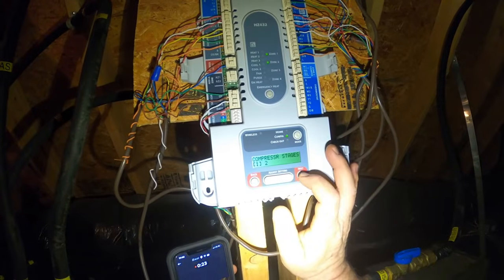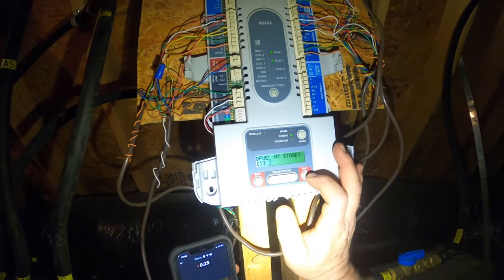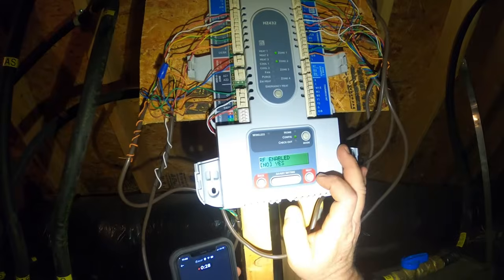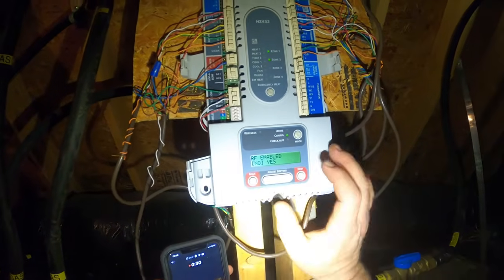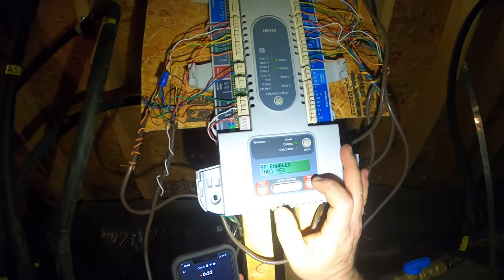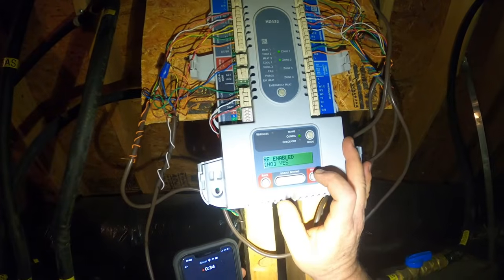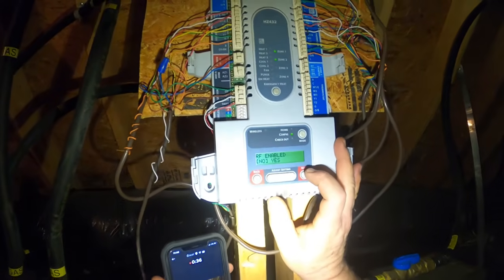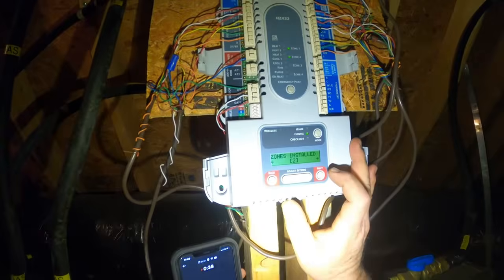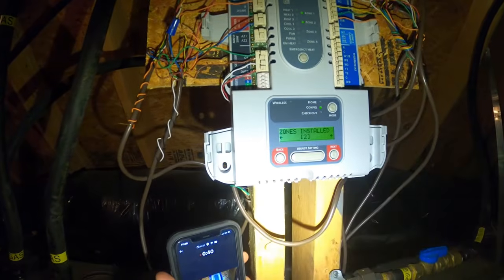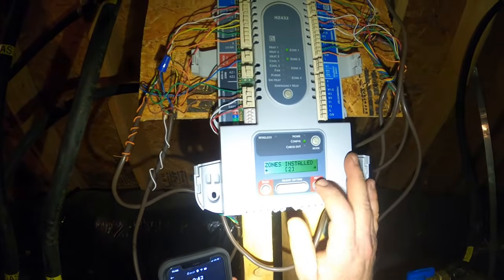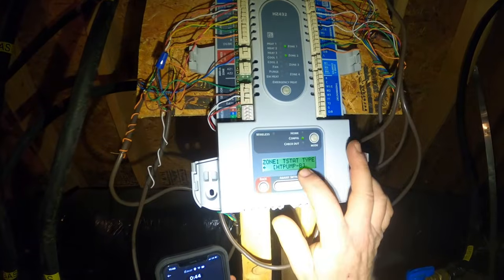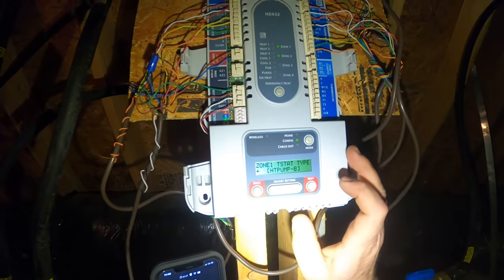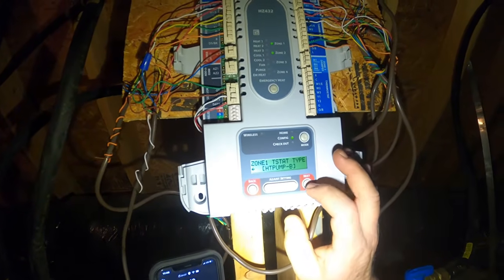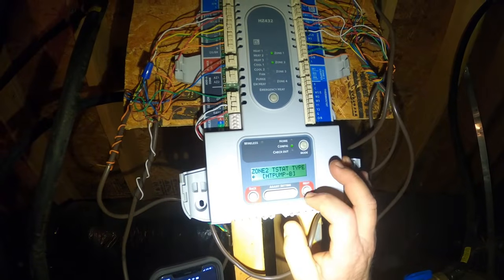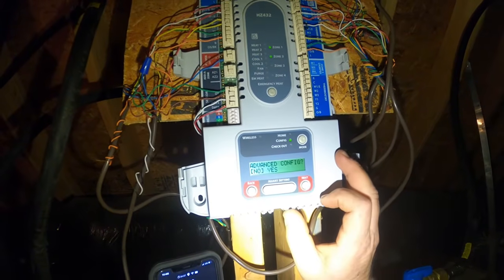Compressor stages, we have a single stage heat pump outside. We have a single stage furnace up here. We're not using the RF enabled, like a communicating wireless thermostat or any other devices like that, so we're going to leave that at no. The zones installed, we have 2. We have a heat pump, but we're going to use B because it energizes in heat, not cooling. Same for the second thermostat.